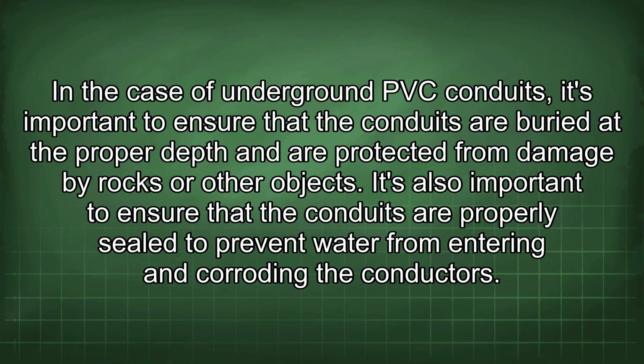In the case of underground PVC conduits, it's important to ensure that the conduits are buried at the proper depth and are protected from damage by rocks or other objects. It's also important to ensure that the conduits are properly sealed to prevent water from entering and corroding the conductors.